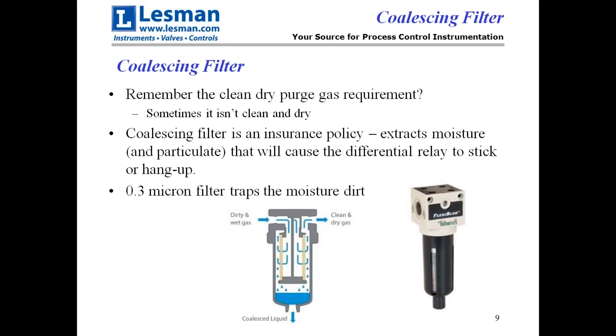We put a coalescing filter in here. In order to make this work, you need clean, dry purge gas going out that dip tube. Sometimes it isn't clean or dry. So the coalescing filter is like an insurance policy that drops the moisture out. It's got a 0.3 micron filter that not only takes the dirt out, but traps oil and water that drops out the bottom and sits in the bowl.